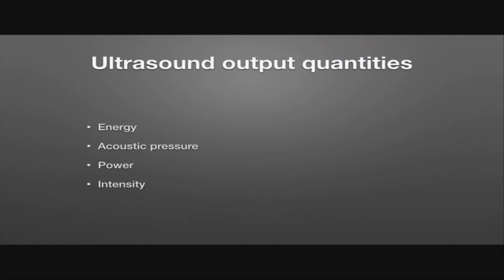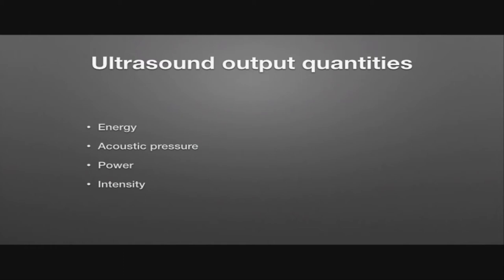It's the ultrasound output quantities that are going to be related to the bio-effects we're talking about. There are different ways of quantifying how much energy goes into the body with ultrasound. Energy is the total work done. Acoustic pressure is the compression of the sound wave. That leads to power, which is the energy per second that is transferred, and intensity — probably the most useful parameter — which is the power per unit area. So intensity gives us an idea of both the power for a given volume of tissue as well as that transfer per second.